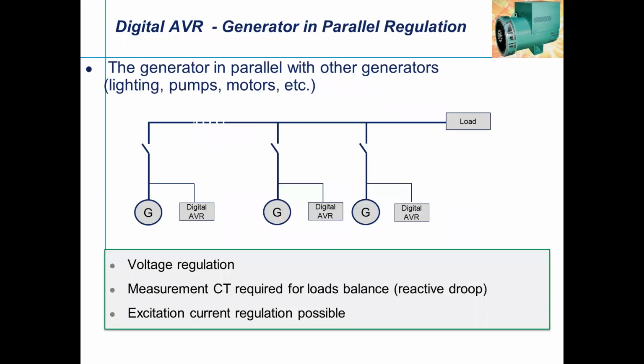So this is how the parallel operation works. Earlier, there were controllers like DEIF or Woodward. They talk to each other. They means when the generators are in parallel operation, with three generators, they communicate with each other. That is how the system requirement is. The same feature is available to communicate between the AVRs. So the digital AVR can communicate with each other. When there is a load demand, how much we want to increase or decrease, we can play with this digital AVR. One is the voltage regulation.